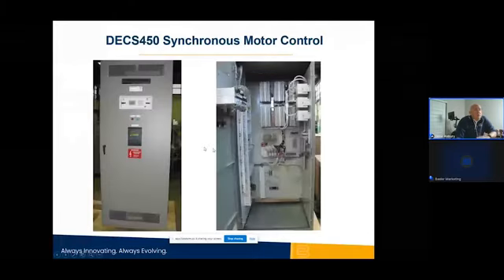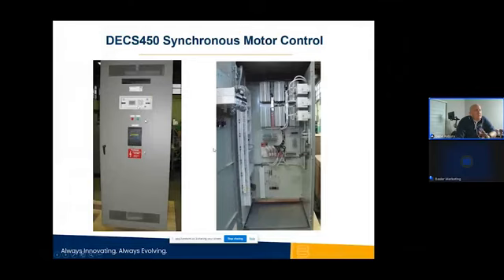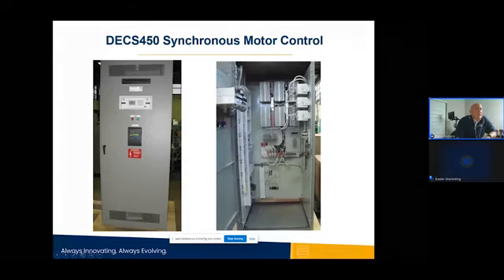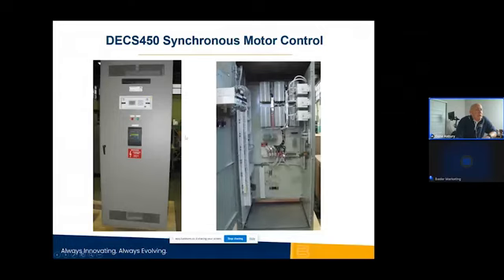So if you need more than 200 amps, we can go with the DECS450 synchronous motor controller. Basically, all of our controllers can work with synchronous generators or motors. This 450 is using, I'm thinking, a 400 amp half wave conversion bridge, so it can only force in the positive direction. It's got a freewheeling diode on the output.